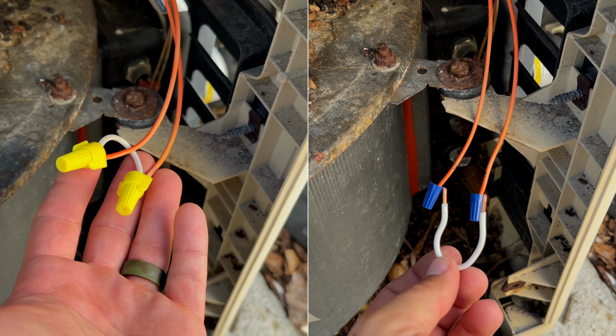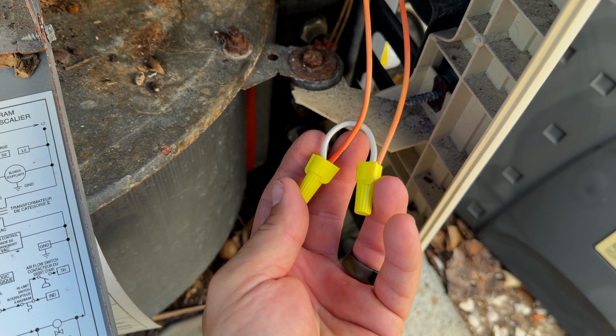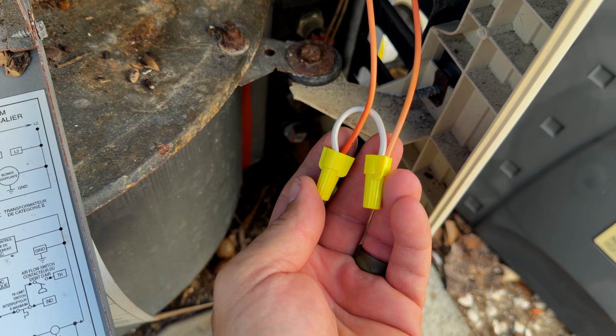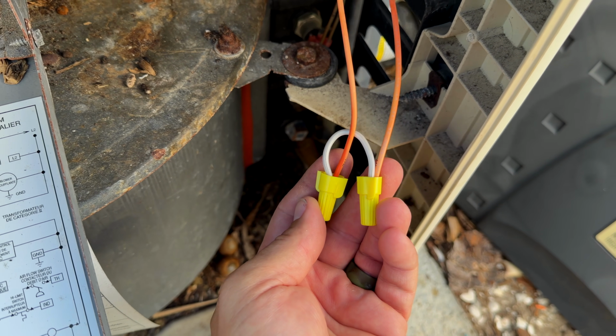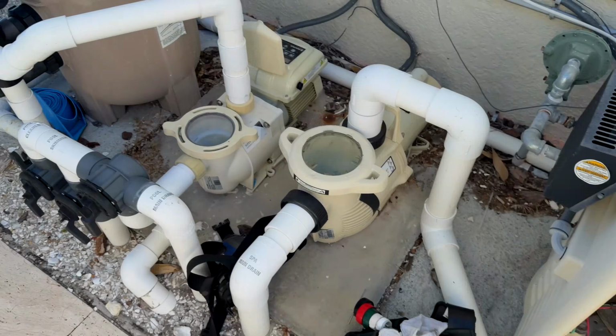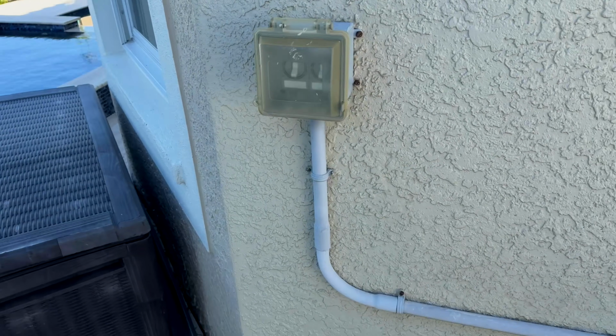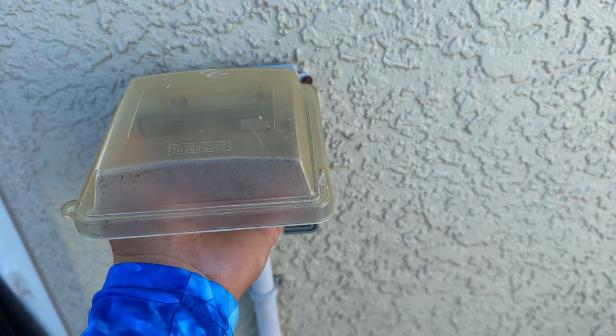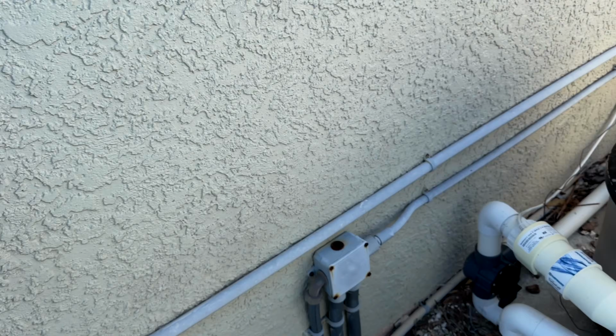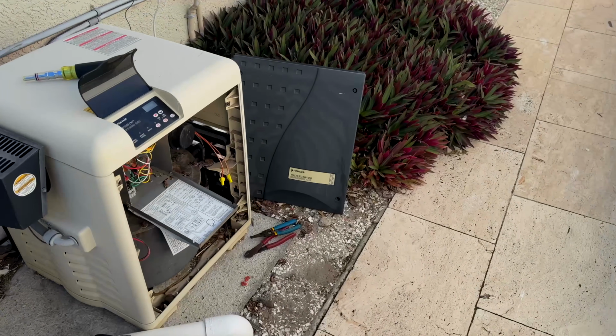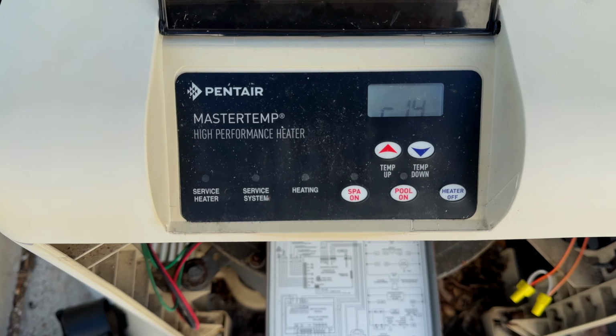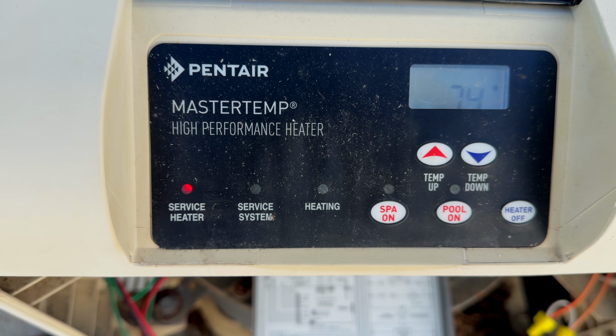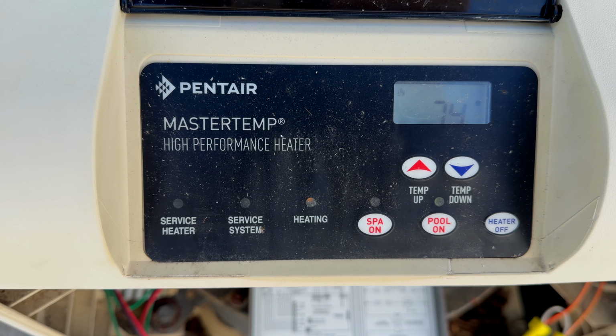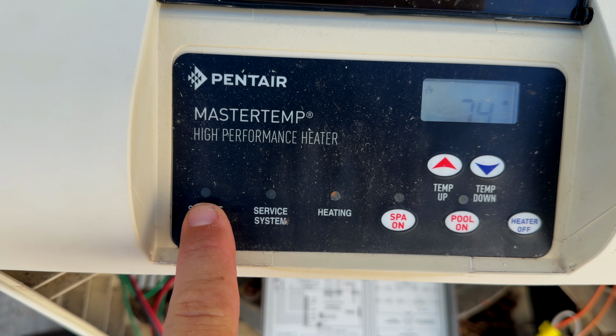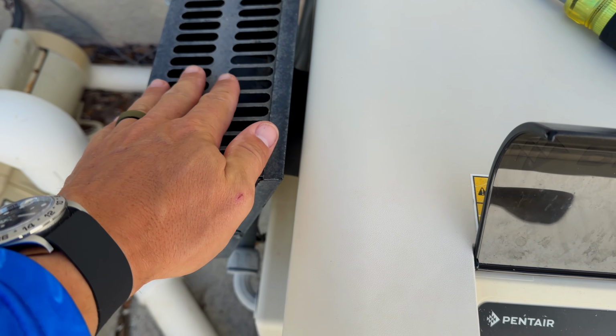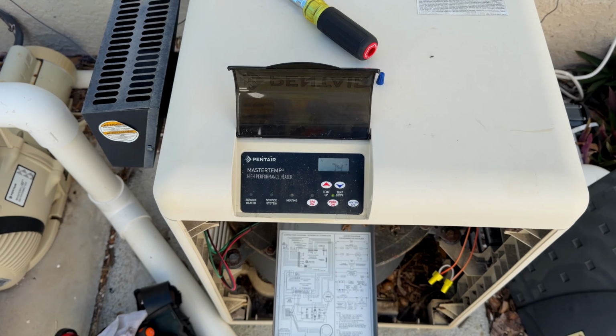And you'll see what it looks like when we're done. All right, so you can see now I created basically a loop. This is simulating a closed high limit switch here. So what we're going to do now is turn the system back on. And again, I apologize for the noise, but let's take a look at this heater. All right, you see the service heater light is on at this moment, but you see it just shut off now. That's a great sign. And now you can hear the fan come on, so that's another good sign. Let's see if this thing fires up.